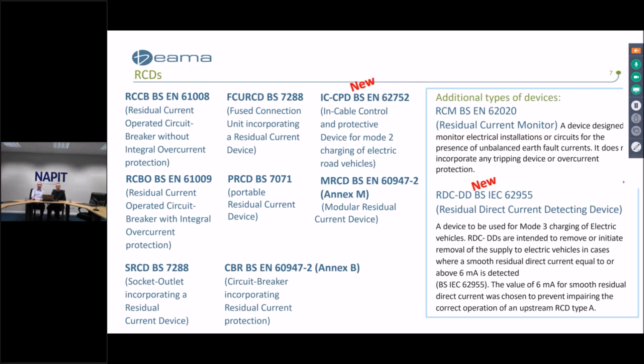SRCDs are not covered by a BS EN, but by a purely British standard, BS 7288, as are fused connection unit RCDs, also covered by BS 7288. And then PRCDs, or portable RCDs, again covered by a purely British standard, BS 7071. There is also a product called a CBR, which is a circuit breaker with residual current protection, and that's covered by BS EN 60947-2, and normally used in more commercial and industrial applications.